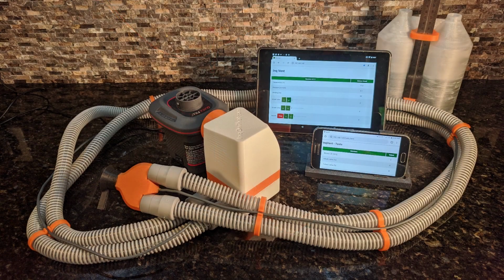Now we need to talk about lungs. Obviously, lungs come in many different sizes, and depending on conditions, different pressures are necessary. Using the web interface, all parameters will be configurable, including breathing frequency, inhalation rate, peak pressure, resistive pressure duration, plateau pressure, elastic pressure duration, and rest duration. It is expected that InqVent will be able to handle all extremes of patient requirements. For this demonstration and for baseline development, a breath volume of 500 milliliters at a peak pressure of 10 centimeters of water will be assumed, which brings us to the test lungs.